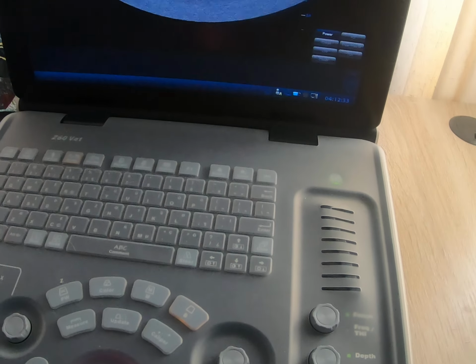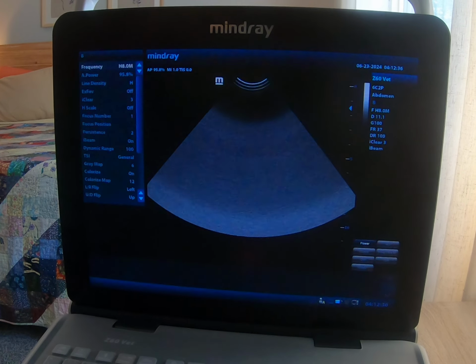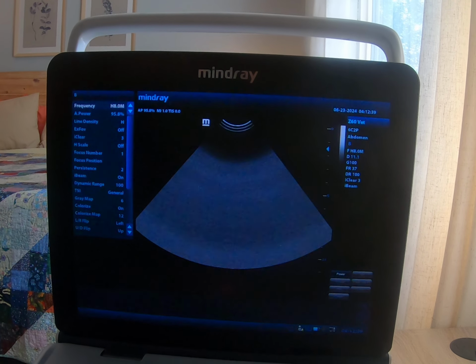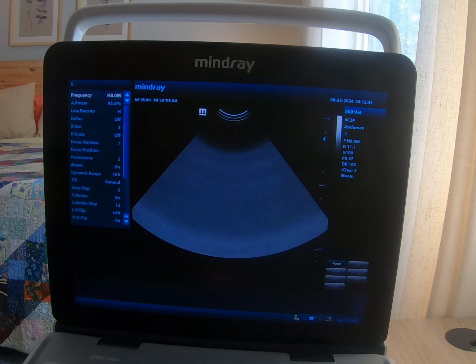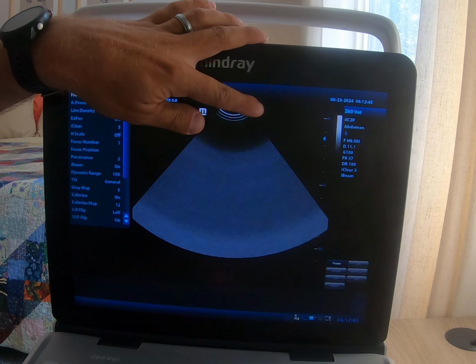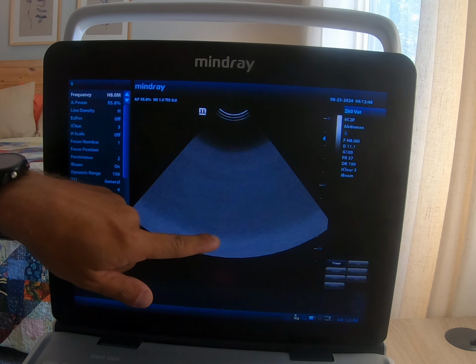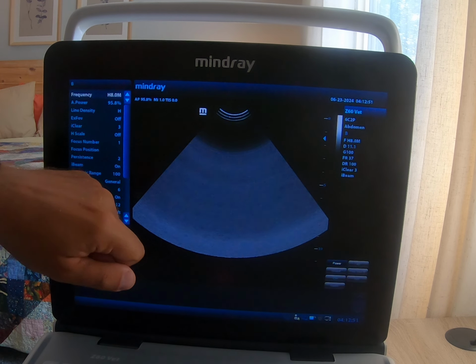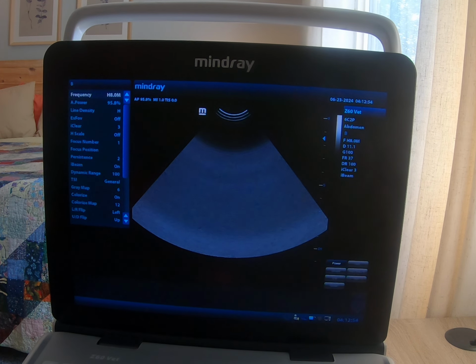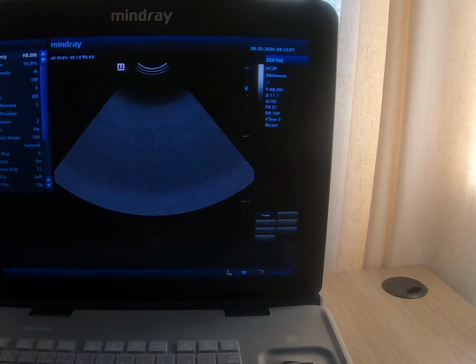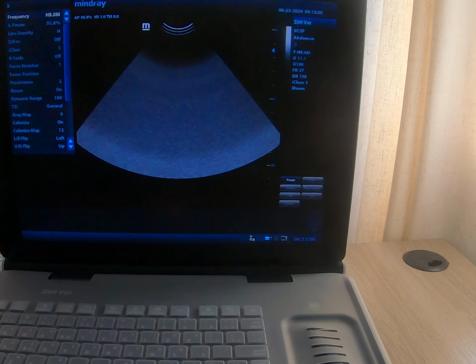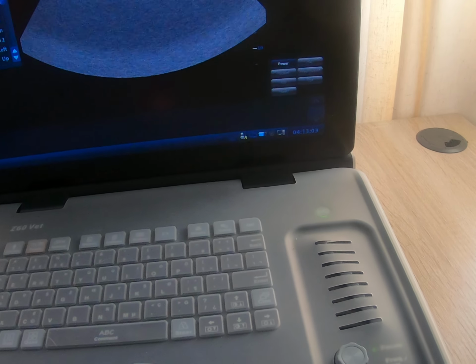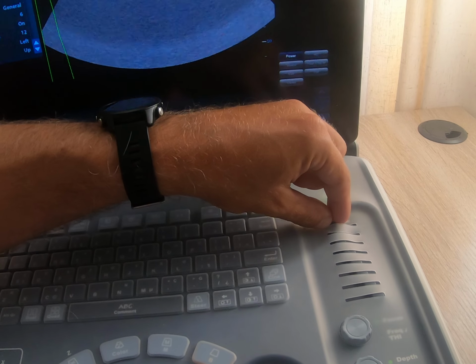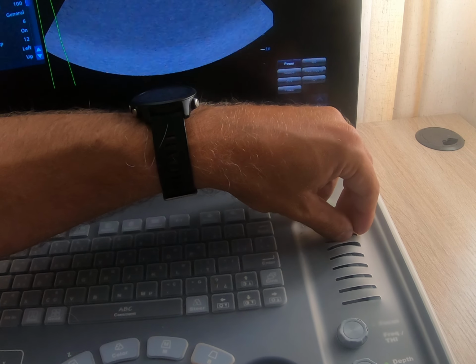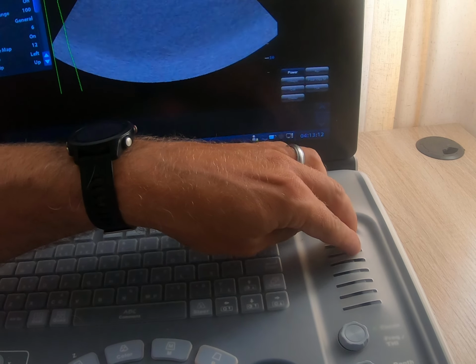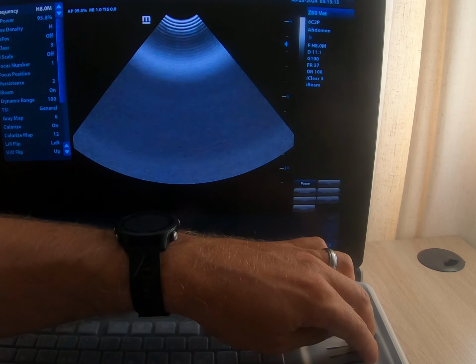So what we can do, let's look at that whole screen again. And get that right there. That looks good. All right, so if I want, I can actually change the time gain compensation in the near field, or I can change it all the way down here on the far field. So if I wanted just to change it in the near field, what I would wind up doing is just altering the top buttons on here. So if I wanted to just alter these guys, and let's say I wanted to change the gain and make it darker on just the near field.